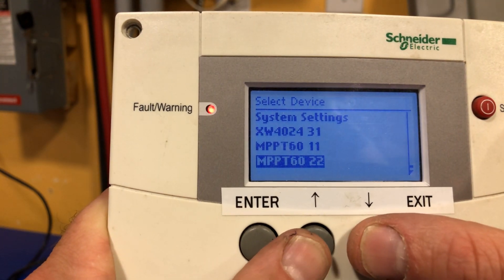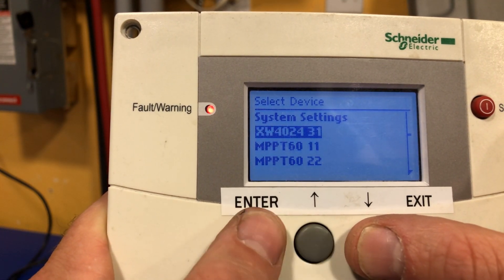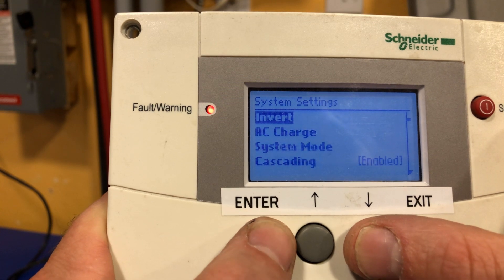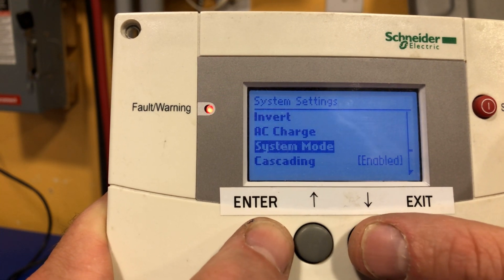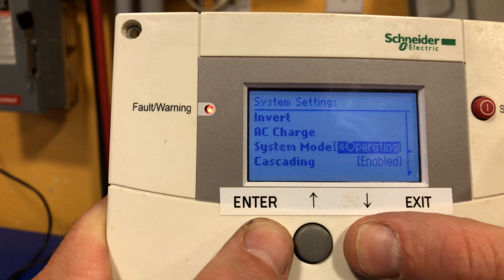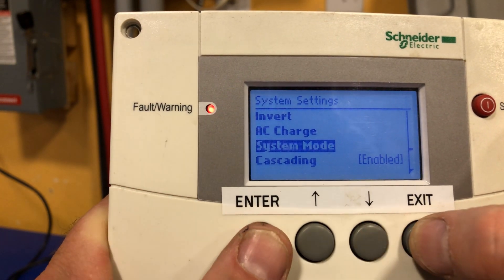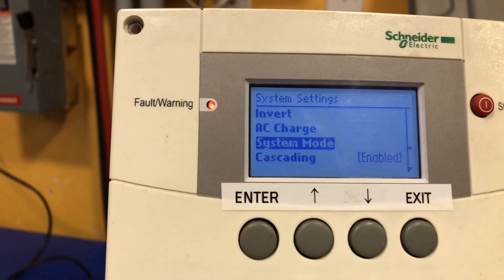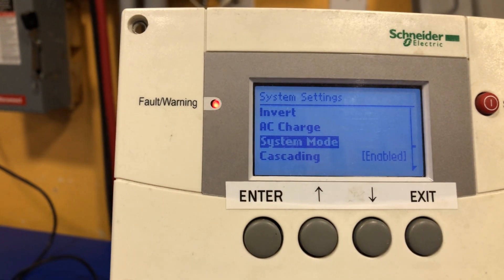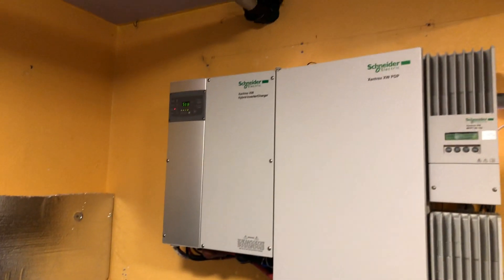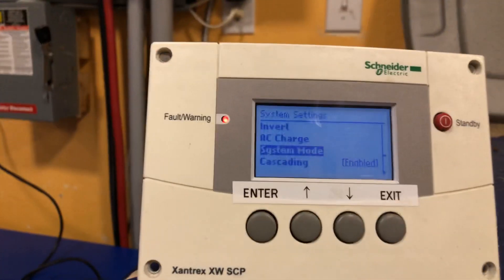So let's go ahead and change that. Under system settings, let's go ahead and set system mode, press enter, down, enter. Now the system is in standby. You can see that on the inverter up here — the inverter reads STB for standby. Now we can make those programming settings to the unique ID.